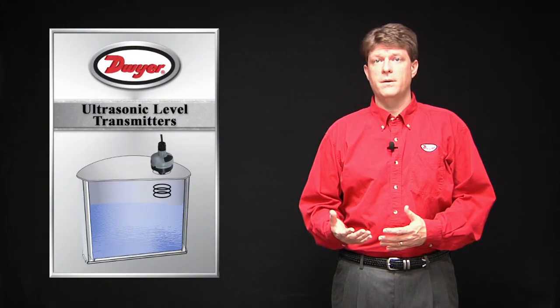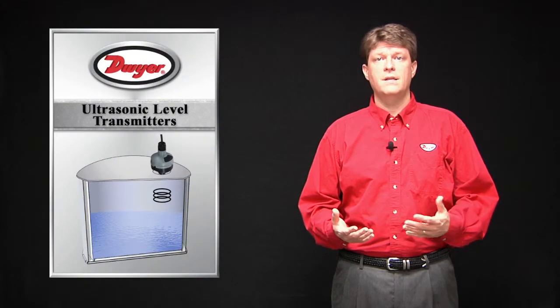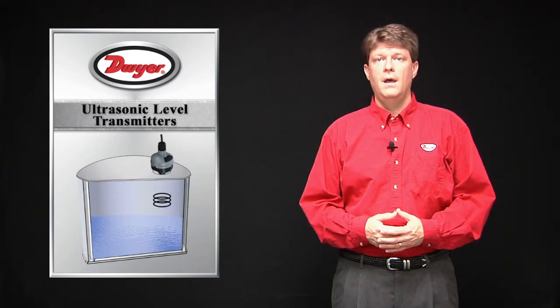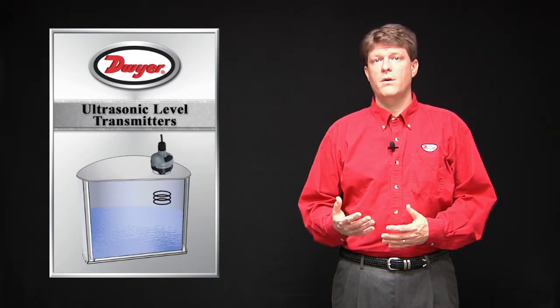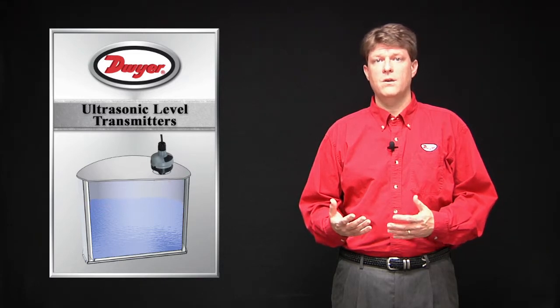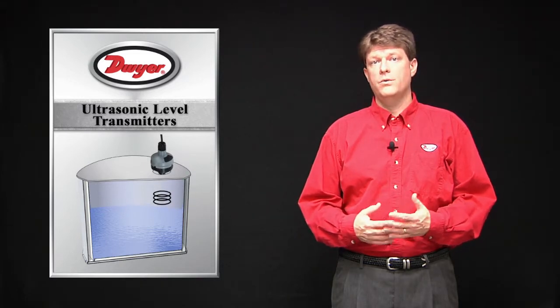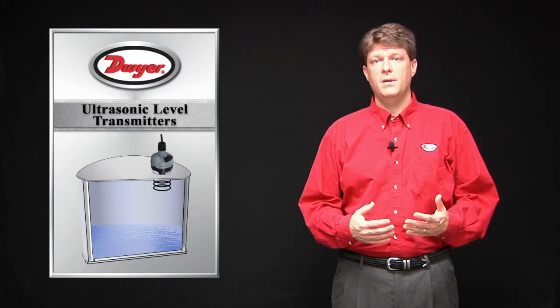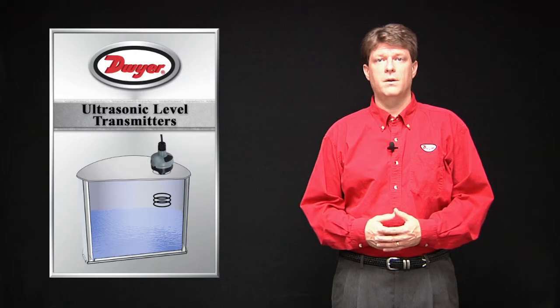Ultrasonic level transmitters are a non-contact level sensing technology that works similarly to radar or sonar. The piezoelectric transducer generates high frequency sound waves in the ultrasonic range. Ultrasonic frequencies are above the levels of sound that humans can hear, typically between 40 and 200 kHz for a level transmitter.